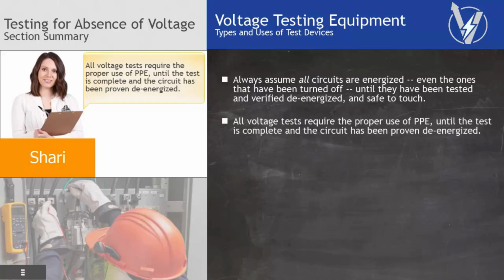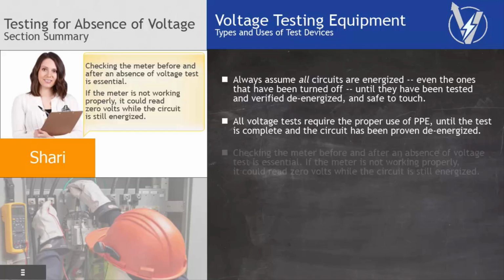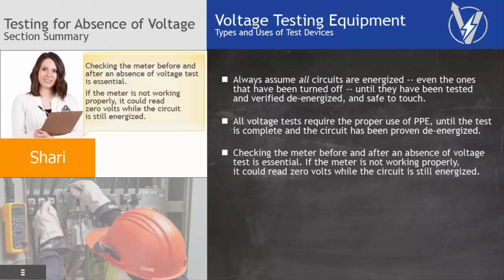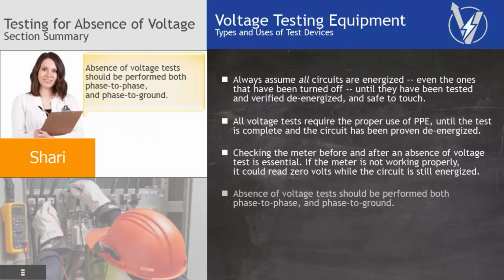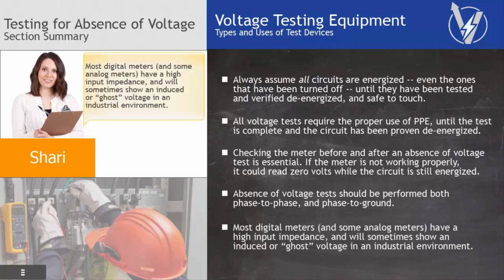All voltage tests require the proper use of PPE until the test is complete and the circuit has been proven de-energized. Checking the meter before and after an absence of voltage test is essential. If the meter is not working properly, it could read 0 volts while the circuit is still energized. Absence of voltage tests should be performed both phase-to-phase and phase-to-ground. Most digital meters and some analog meters have a high input impedance and will sometimes show an induced or ghost voltage in an industrial environment.